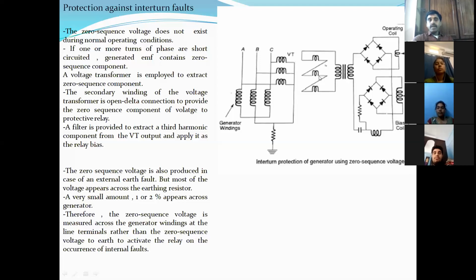So what is the mechanism here? After the zero sequence voltage is given to this side, the secondary winding of the voltage transformer is open delta, as I said, and it is used to provide the zero sequence component of voltage to the protective relay. A filter is provided to extract the third harmonic component from the VT output, and apply it as a relay bias. That means the third harmonic is extracted whenever the zero sequence component is there. The third harmonic that is extracted is used for the relay operation.